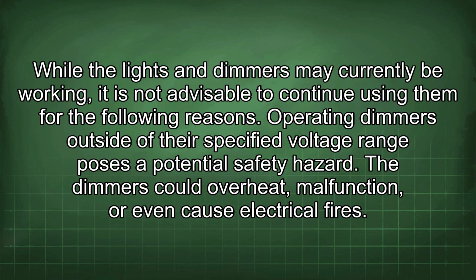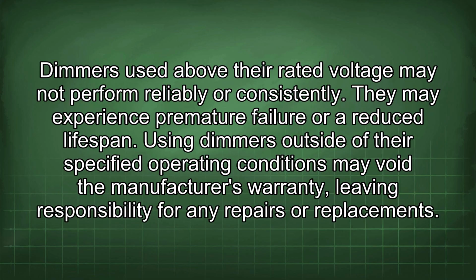While the lights and dimmers may currently be working, it is not advisable to continue using them for the following reasons. Operating dimmers outside of their specified voltage range poses a potential safety hazard. The dimmers could overheat, malfunction, or even cause electrical fires. Dimmers used above their rated voltage may not perform reliably or consistently. They may experience premature failure or a reduced lifespan.